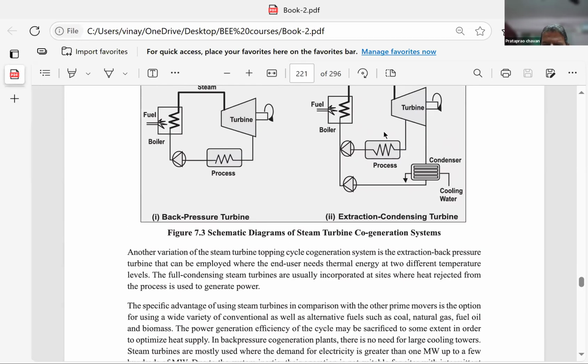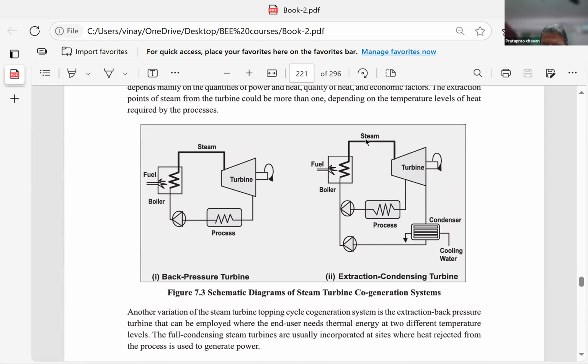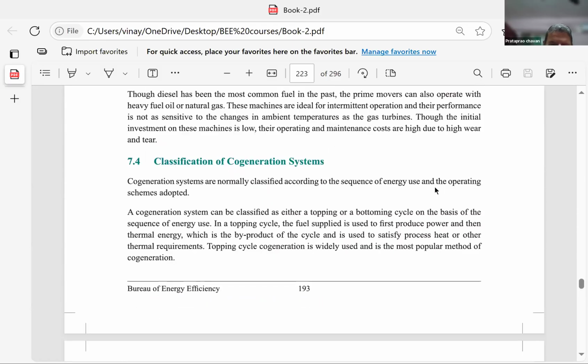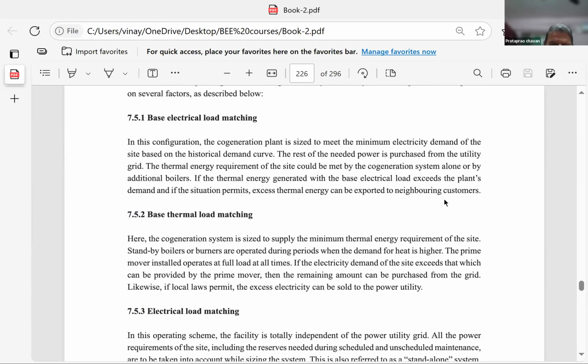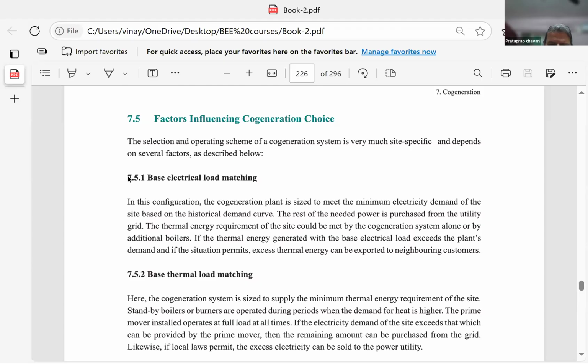Here, this figure shows fuel used in the boiler. Steam is apportioned to the turbine and to the process. Electricity is generated here, and heat requirement is met here. If you design this system primarily to match the electrical load of the industry, it is called base electrical load matching. That means electricity is of primary importance. You design the turbine or generator so that partially the heat requirement of the industry can be tapped from the turbine, while also fulfilling the condition of generating a certain amount of electricity. When you fulfill this as an energy auditor, it is called the method of base electrical load matching.